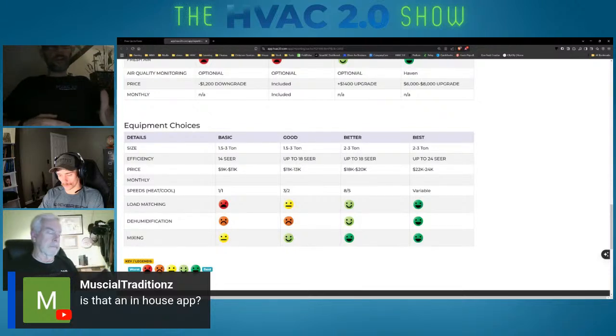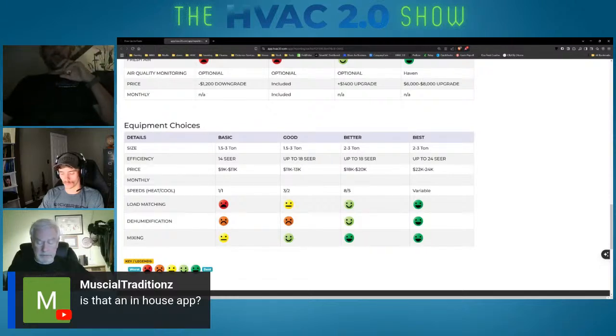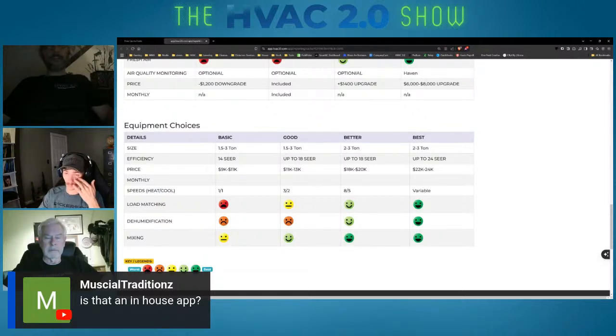There's some other things like likely load range, offering to take static pressure, which can be done a number of ways - you can use Measure Quick, which is third-party verified, showing people don't have enough ductwork for their current equipment. This helps people be comfortable choosing smaller equipment so it matches the ductwork, particularly if they're not interested in changing out ductwork, which most change-out homeowners aren't, at least on our side of the Mississippi. We also want to make sure they're aware of opportunities for better dehumidification control, because in humid, green grass climates, keeping relative humidity below 50% in homes is really important for avoiding mold.